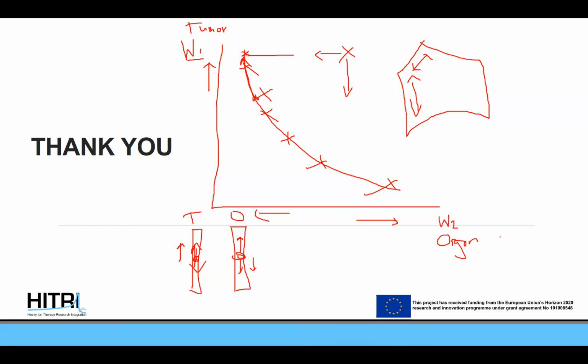There is a huge change in the last 10 years where we do what is called adaptive radiotherapy, where you can take images regularly during treatment and adapt if there is a change. With a CT or with an MRI, you can do both. MR Linacs have been developed exactly for that, with daily adaptation if needed. There is a big problem there because every time you change the plan, you also have to have a new QA test of the plan. So there is usually a big discussion at the moment: when do we do the QA of the new plan, and when do we not?